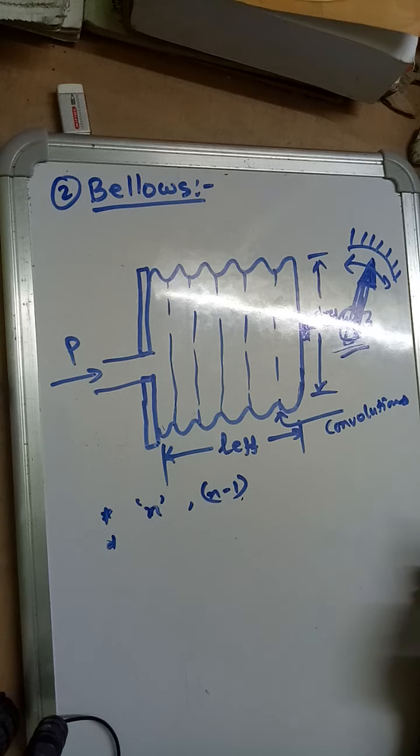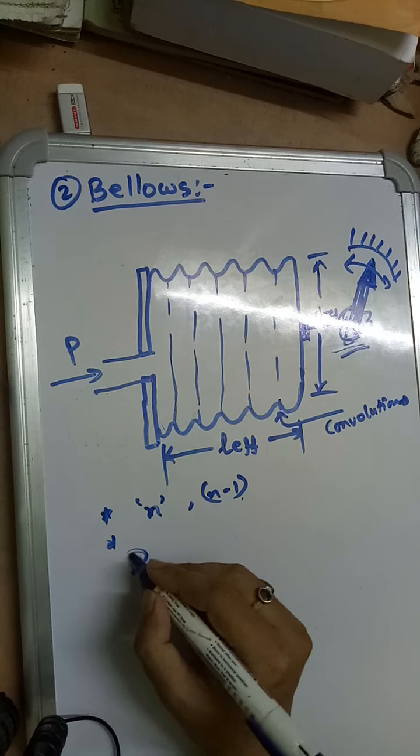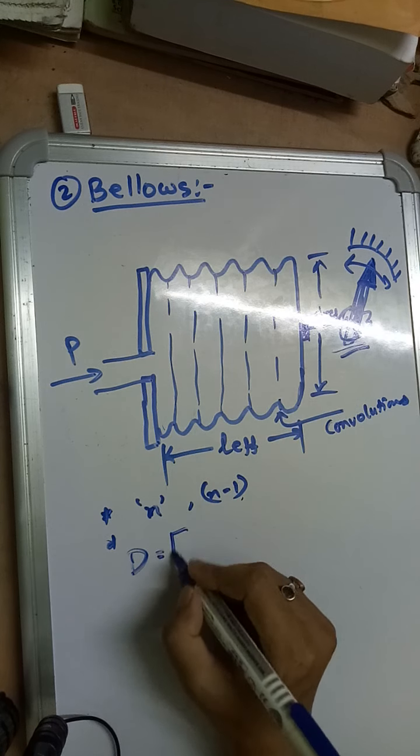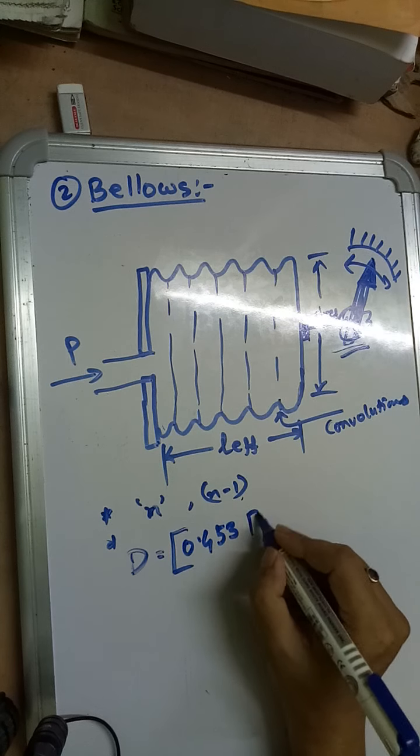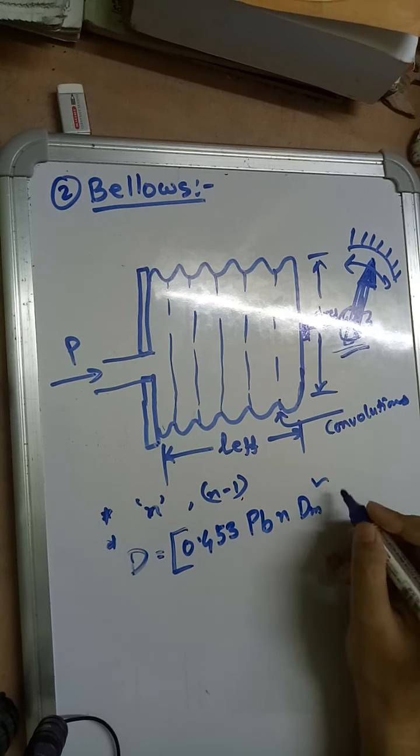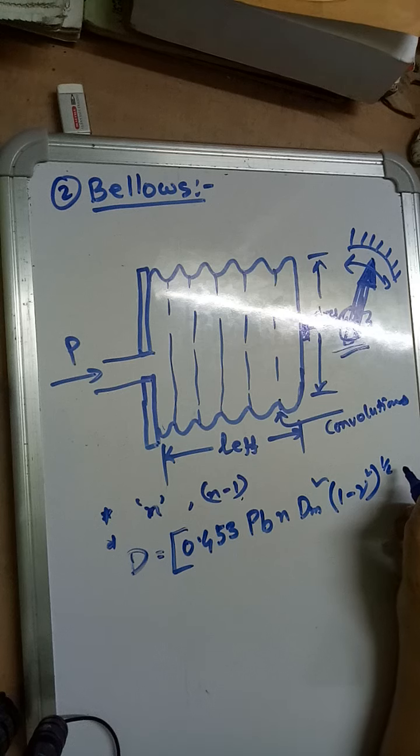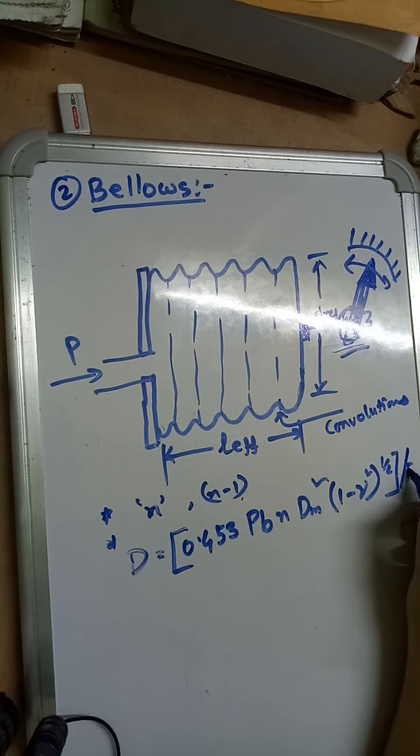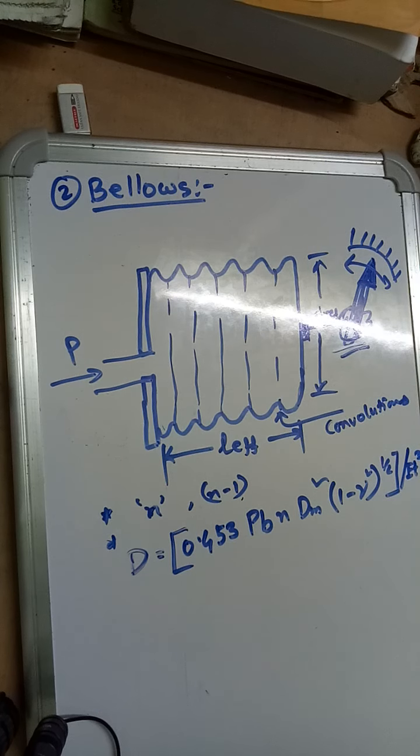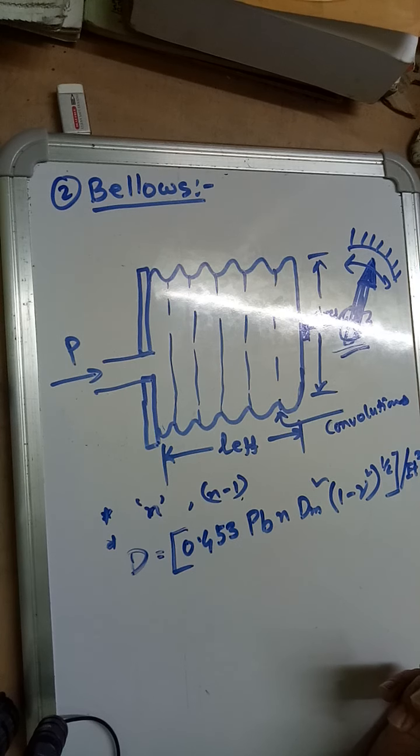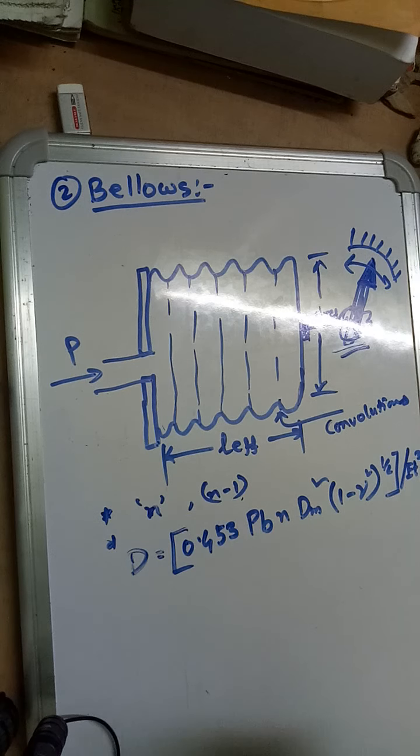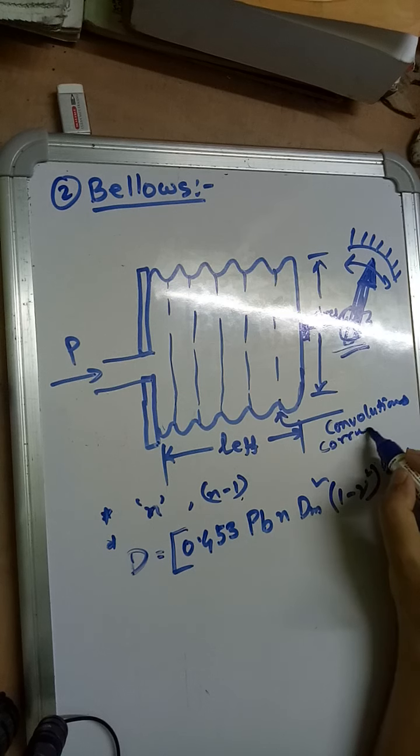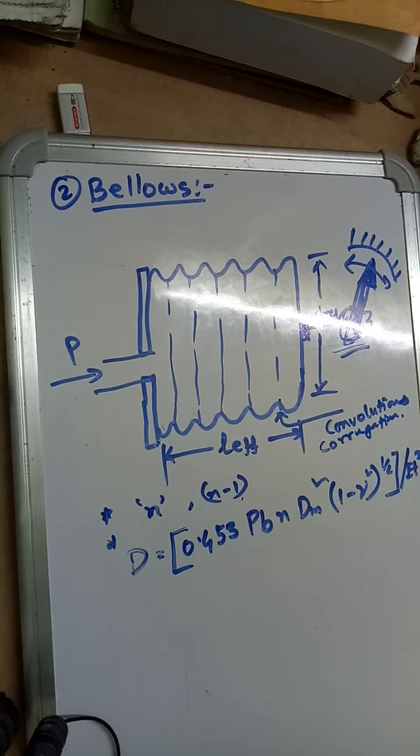The compound action of bending and tension operates the elastic member. In general, the displacement of the bellows element is given by - again, it is an empirical formula - d = 0.453 p b n d_m² √(1 - ν²) / (E t³). Here, p equals pressure, b equals radius of each corrugation. A corrugation means it is called convolution or corrugation.